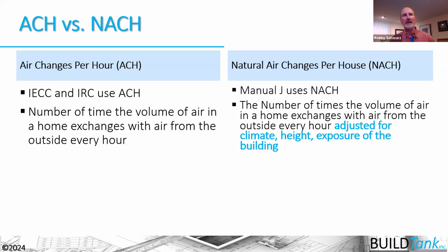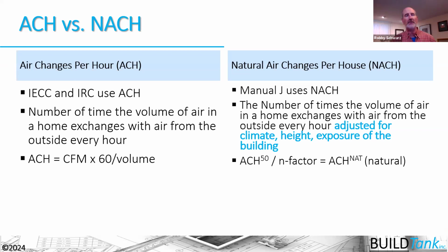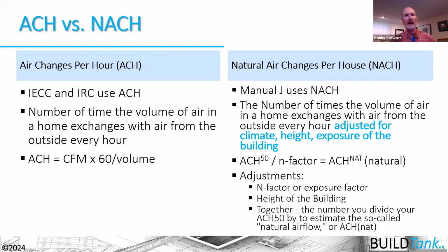Now, for NACH, it's the number of times the volume of air is exchanged with air from the outside, but it's adjusted for the climate that house is in, the height of the house above the grade outside, and the exposure of that building to wind outside. So the number is getting adjusted here. The air change per hour calculation is described here, and the natural air change per hour calculation adds in this N factor number to adjust the air change per hour number and make it a natural number, which again is adjusting for climate, height, and exposure of the building to wind. So that's where the N factor comes in.